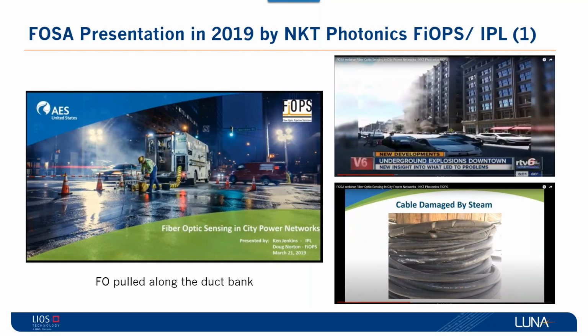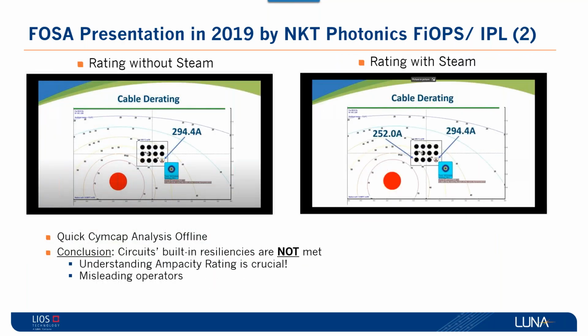From an asset point of view, in 2019 there was a FOSA webinar, as I mentioned, where we talked about pulling fiber optic in the duct bank to monitor steam lines that were affecting and damaging the medium voltage cables. On the top right, you can see this event, where a few manhole explosions captured quite a lot of news and brought a lot of negative visibility to the utilities in Indianapolis. But what was great is that with the fiber optic cable sensing system, they were able to monitor each one of those routes and tell the steam company, the utility operating the steam line, that there was a leaking steam line affecting the circuit and the duct bank.